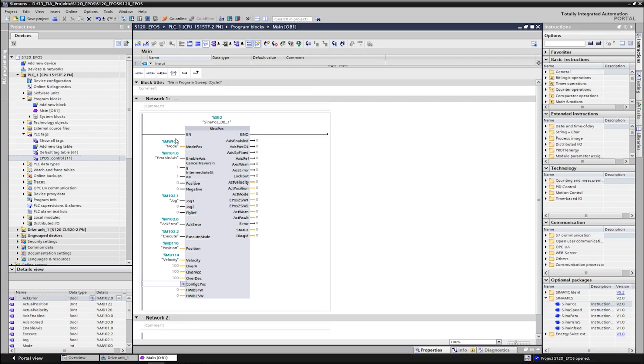For example, bit 0 and 1 stand for the shutdown functions OFF2 and OFF3 and are therefore set to 1 by default. Bit 2 activates the software limit switches. Since we want to use these, we additionally set bit 2 by specifying the converted decimal value 7. The value 7 results when the first three bits of the control word are set. The list of all control bits can be found in the manual.